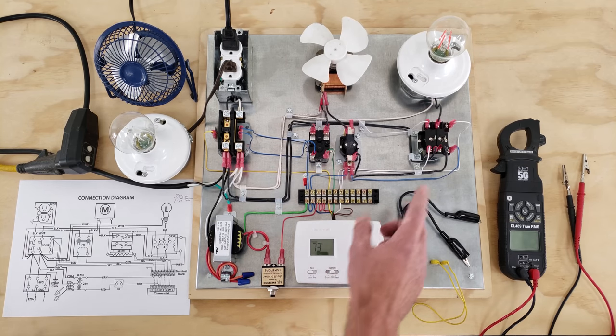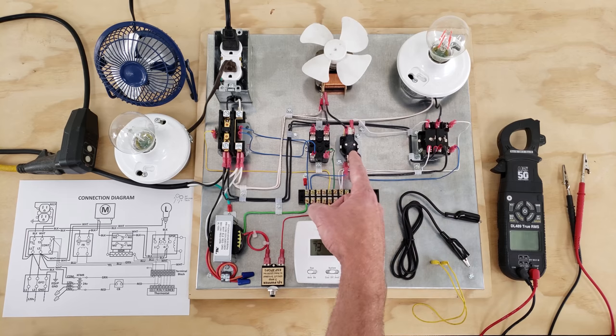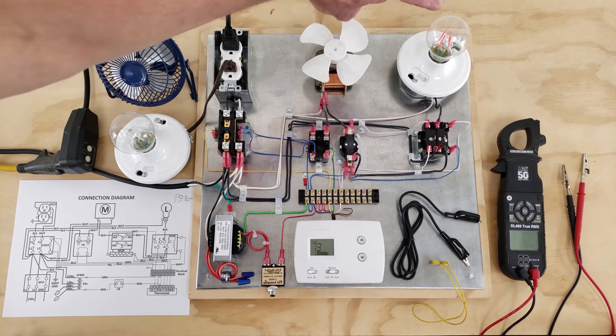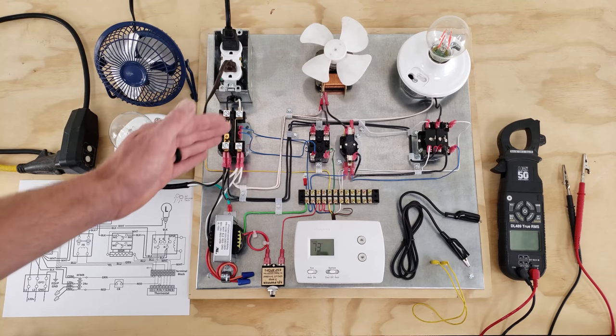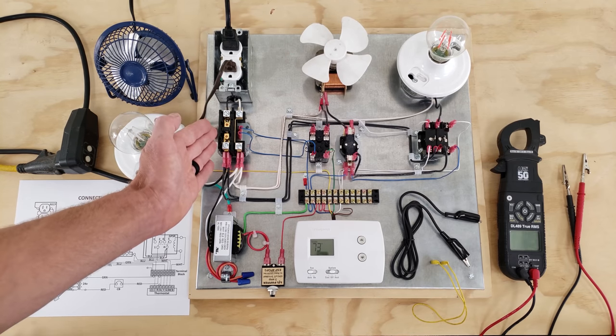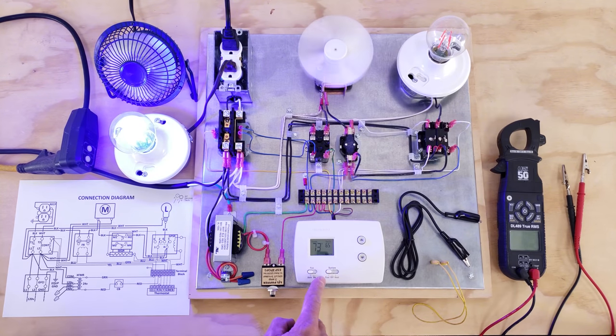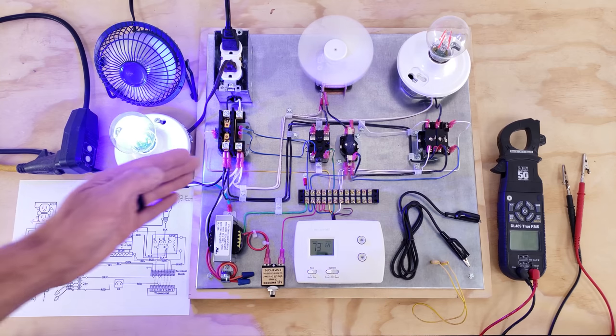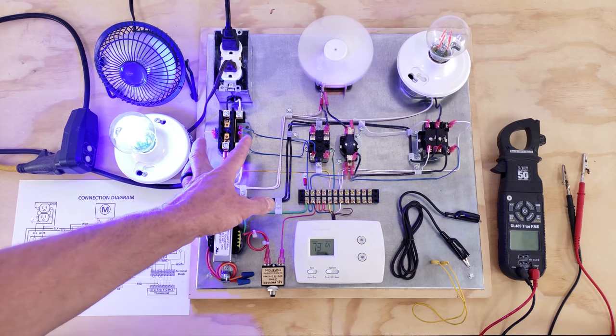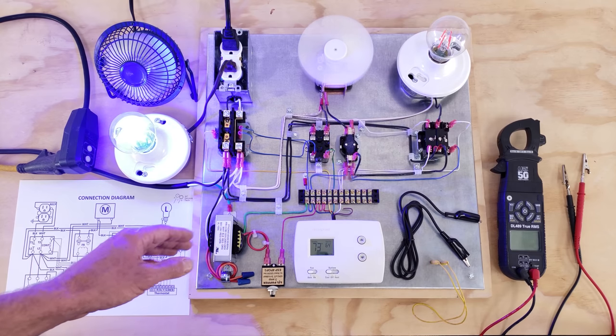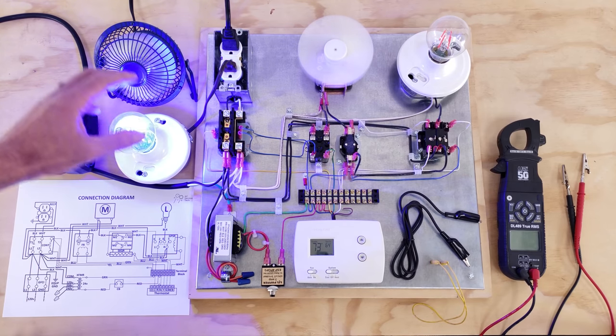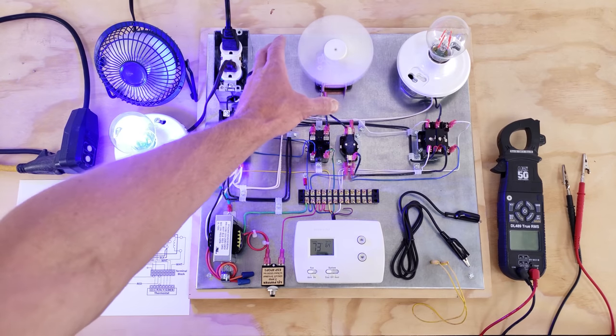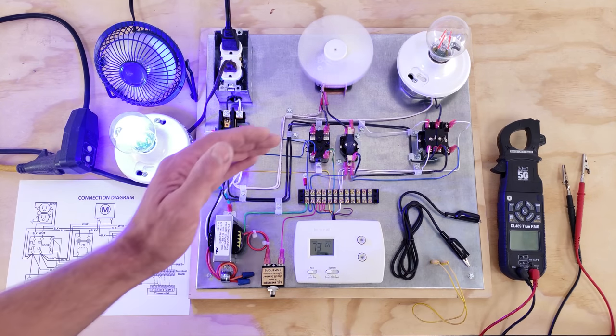So in the case of heat, we're using a general purpose relay and we're using the sequencer in order to power both the light bulb and the fan motor. And now for air conditioning mode, we're using a contactor. And so what we want to do is we're going to turn our thermostat on for air conditioning. And so we want to turn our temperature down. And in this case, it's 65 degrees is what we have it set at, and it's 73 in the building. And so we're using our contactor. We're powering the sides of the contactor, the coil, in order to power our outdoor compressor, our outdoor fan motor, and also our indoor fan motor. So that's how air conditioning works.